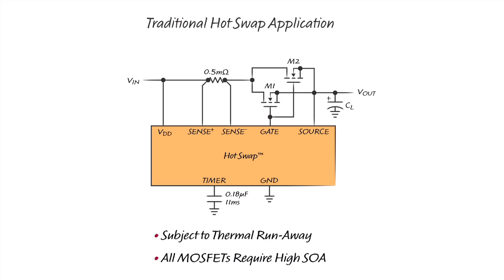When MOSFETs are fully enhanced in this configuration they share current well because their RDS(on) has a positive temperature coefficient that makes hot MOSFETs more resistive, which diverts current into the other cooler MOSFETs. However, when the MOSFETs are regulated by the hot swap controller, the sharing between the MOSFETs is dominated by their threshold voltages, which have a negative temperature coefficient, causing a hot MOSFET to dissipate more power as it heats, leading to a thermal runaway condition.